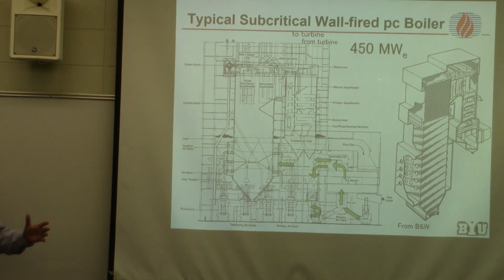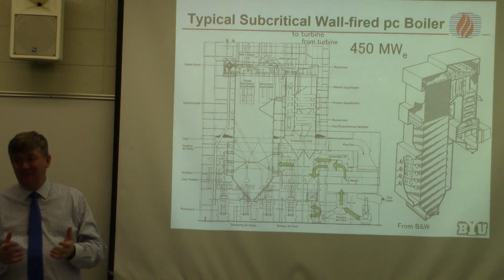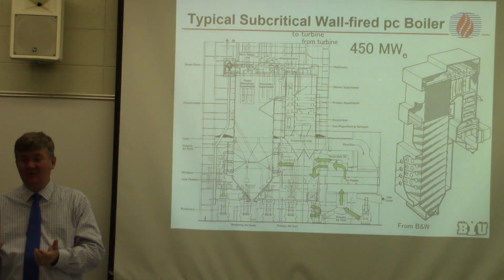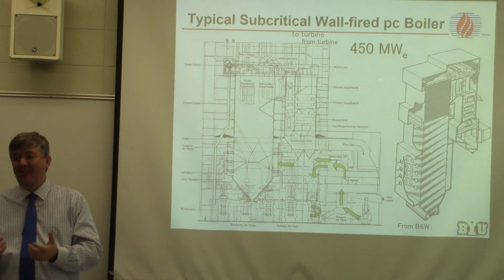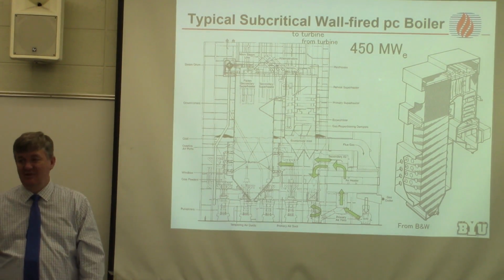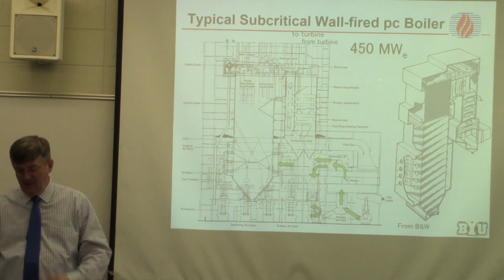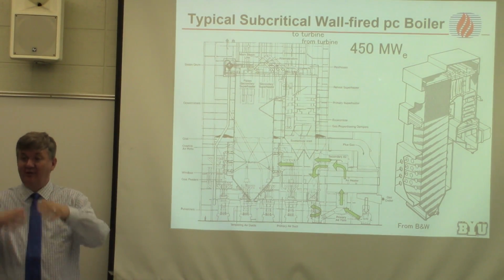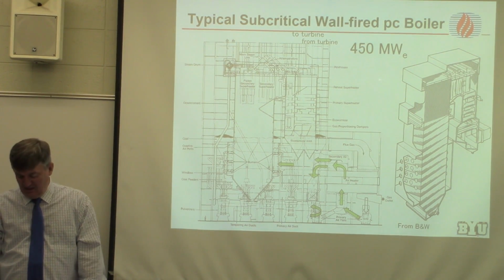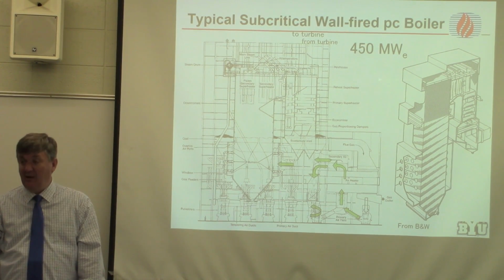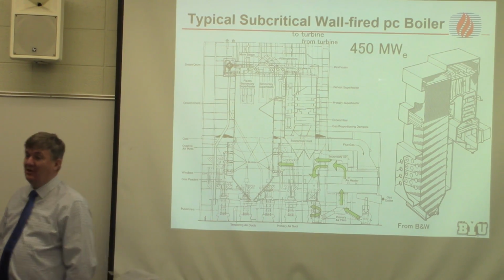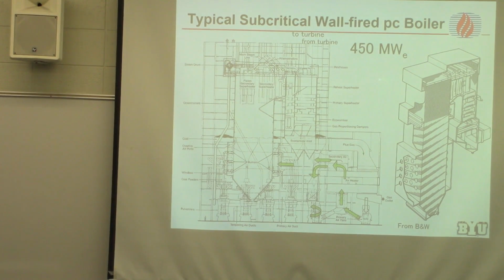And think about this, you're putting hundreds of tons of pulverized fuel in there, and if the flame goes out and then reignites, you have an explosion, which is bad. So the whole building, think of a 30-story building erupting. That almost never happens with coal-fired power plants. It happens with black liquor plants still 1 or 2 times a year somewhere in the world.